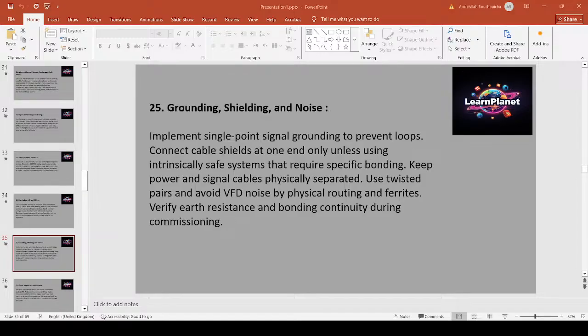Single point signal grounding avoids ground loops in analog systems. In large plants, use equipotential bonding and structured grounding plans. Connect cable shields at one end unless intrinsically safe or specific cable standards require different bonding. Physically separate power and signal cables. Use twisted pair and shielded cables, and ferrites near VFDs to reduce noise. Verify earth resistance and bonding continuity in commissioning. Example: persistent noise on a thermocouple near a VFD was resolved by routing the TC cable away from VFD power lines and adding ferrite cores.